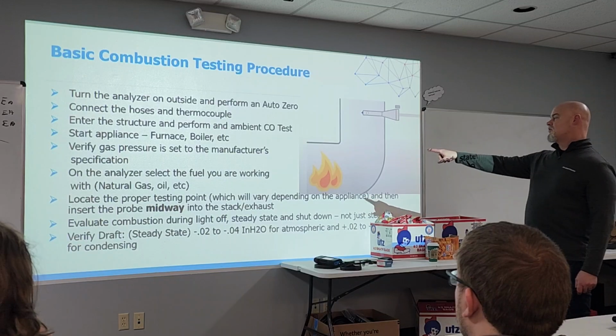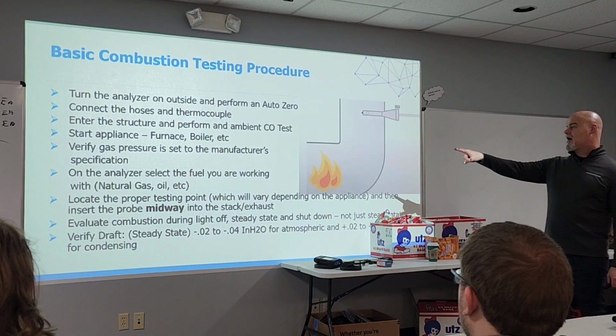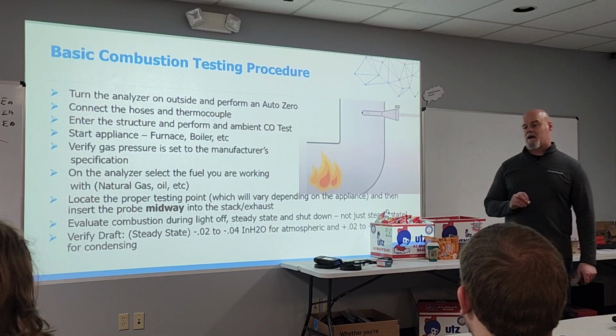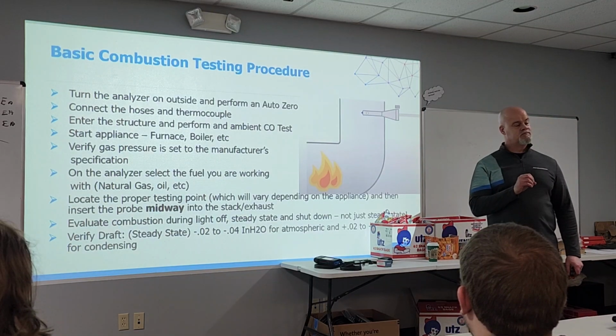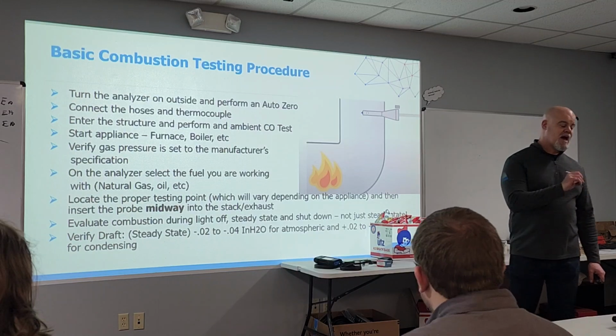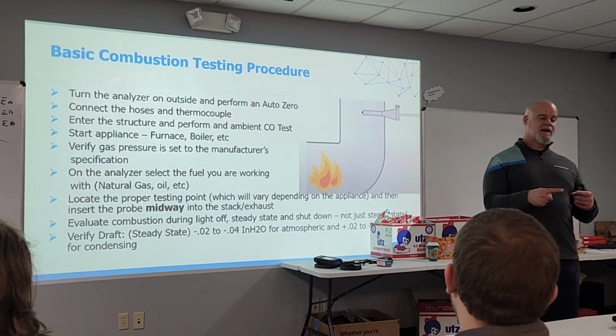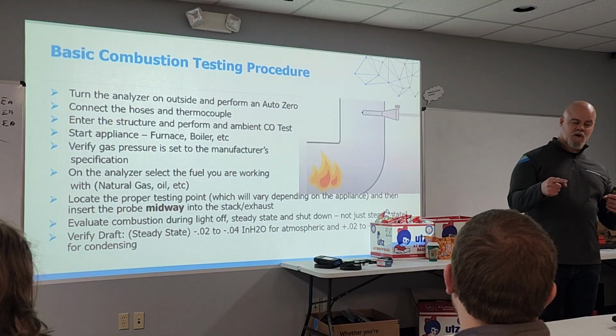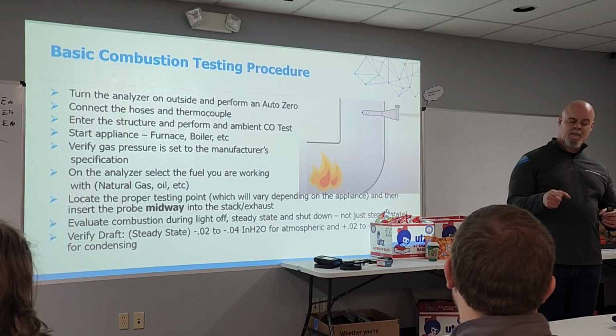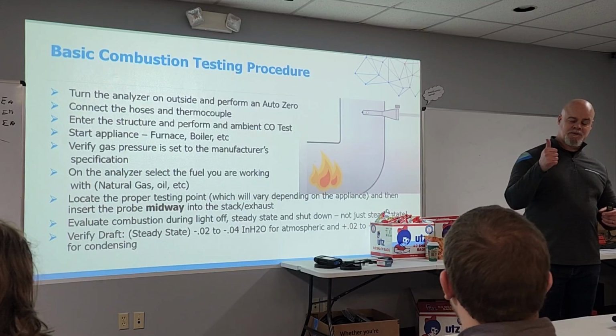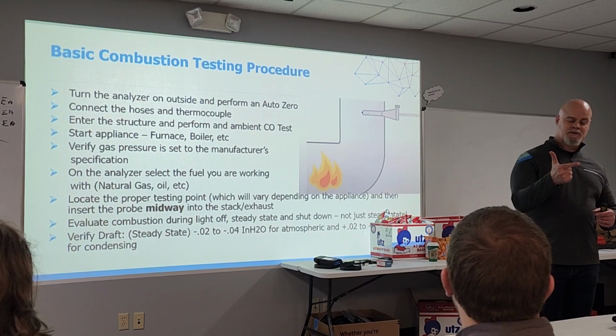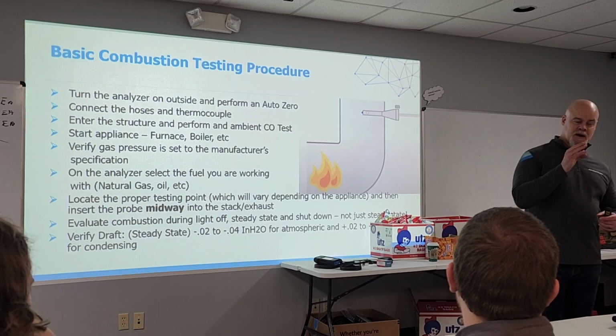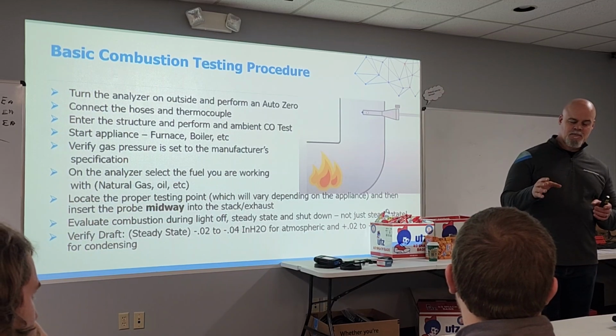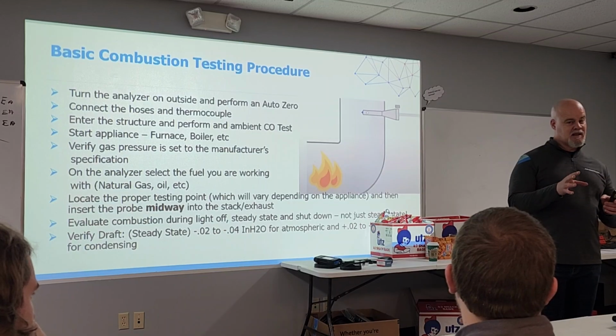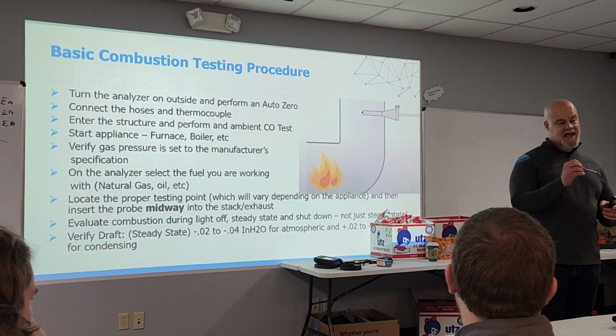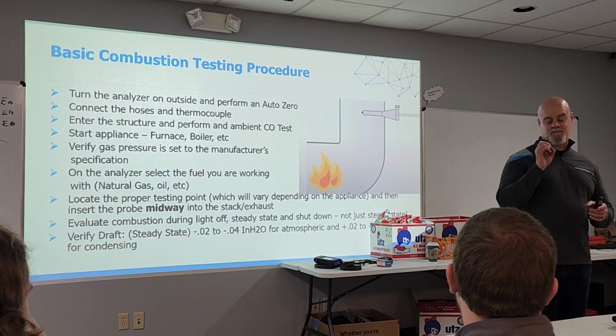Start up the furnace or boiler, verify gas pressure set to the manufacturer's specs, and then on your analyzer, make sure you select the correct fuel that you're working on. Here is why. Every fuel has a coefficient assigned to it. That coefficient is a long, protracted decimal number, anywhere from 8 to 12 places to the right of the decimal point. Now, what's baked into that long decimal number is the BTU content of that fuel and all the chemical properties of that fuel that make it up as an identifier. What your analyzer does is it takes that number, multiplies it by the percentage of oxygen your analyzer is reading at that time. The resulting answer to that math is what gives you your CO2 value.